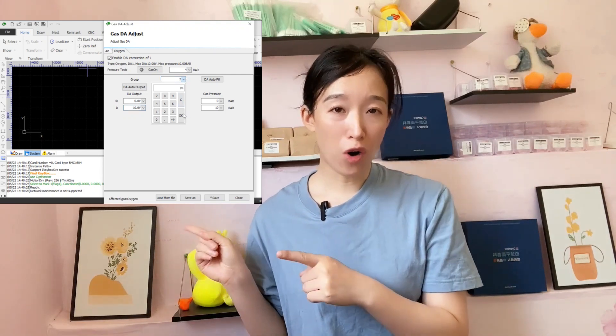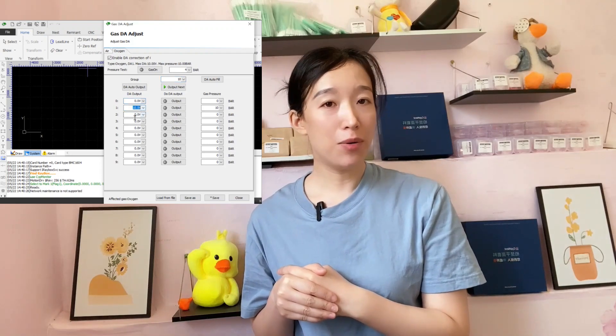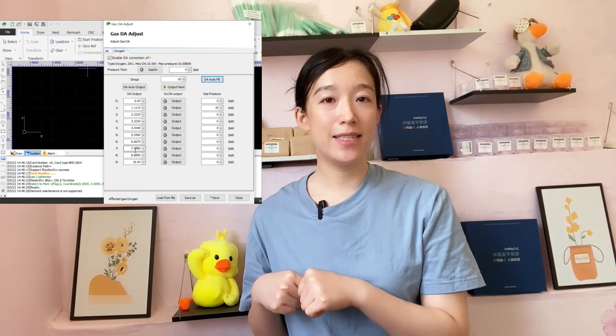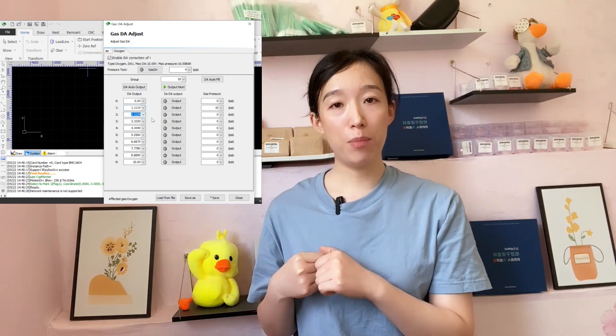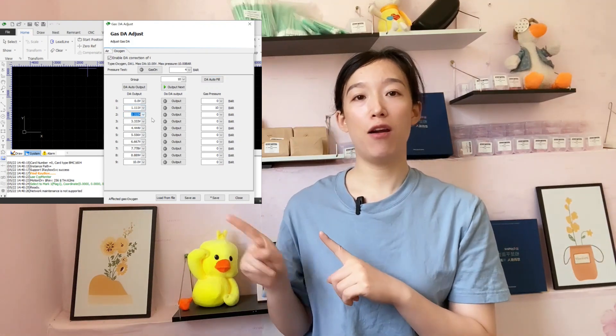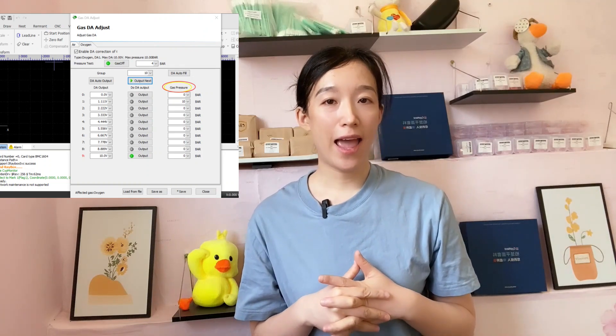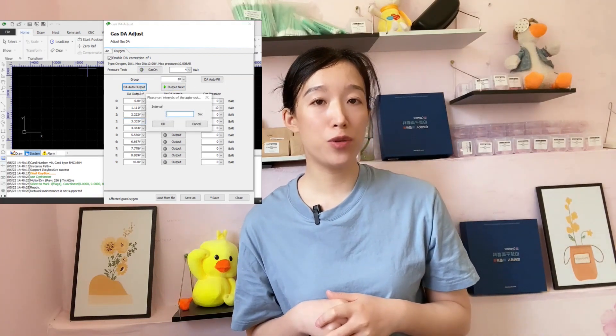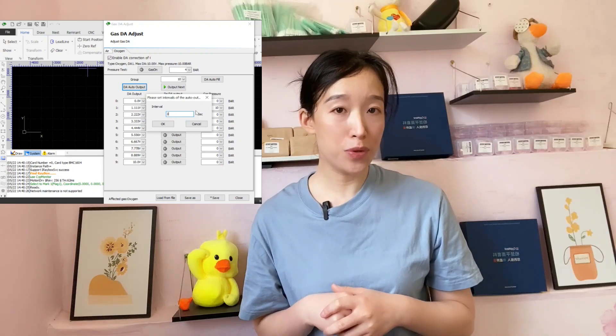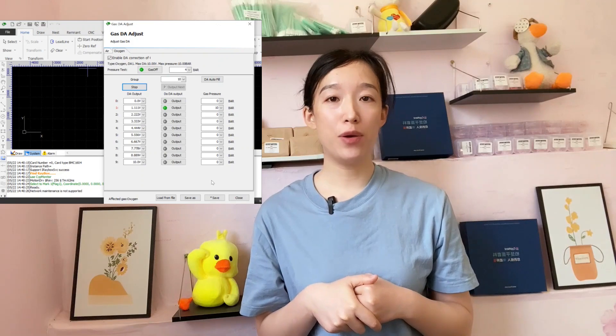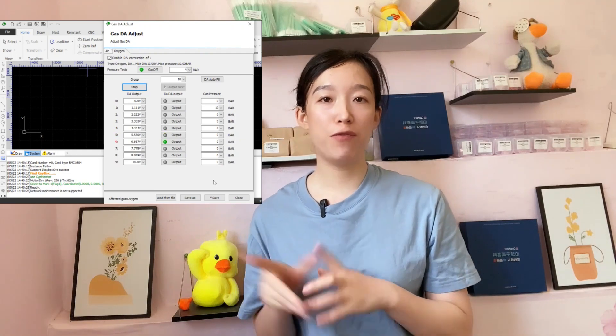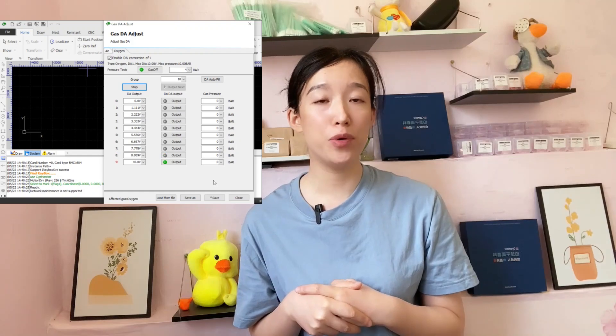We can set it to more groups. The more groups, the higher the fitting accuracy. Generally, set 10 to 15 groups. Then click 'DA autofill' and the system will automatically set the DA distribution values according to the number of groups. We can see the values are filled out automatically. The gas pressure column represents the actual gas pressure we measure.